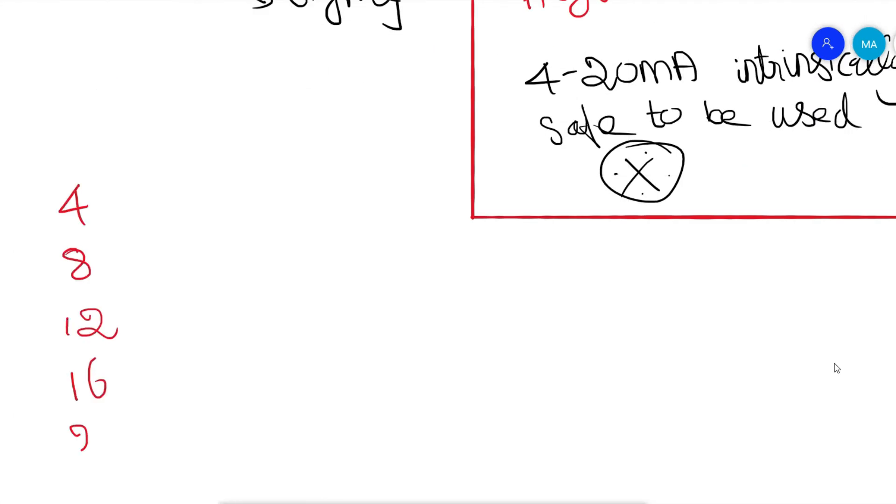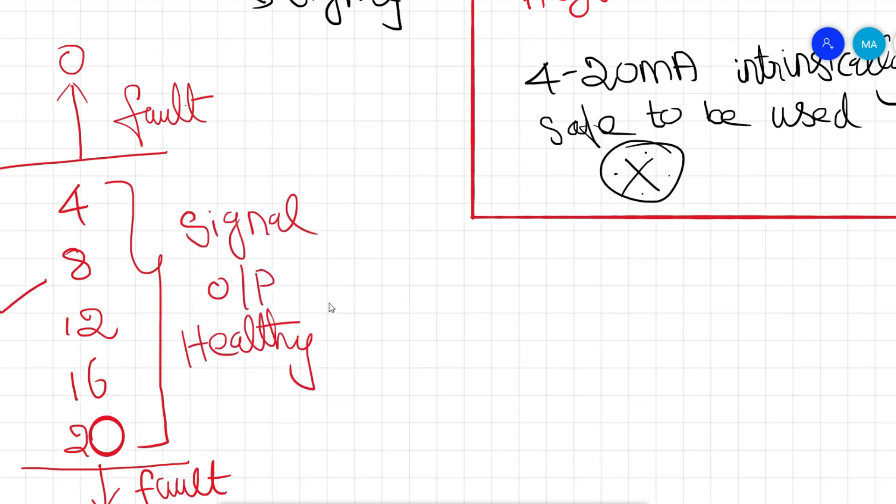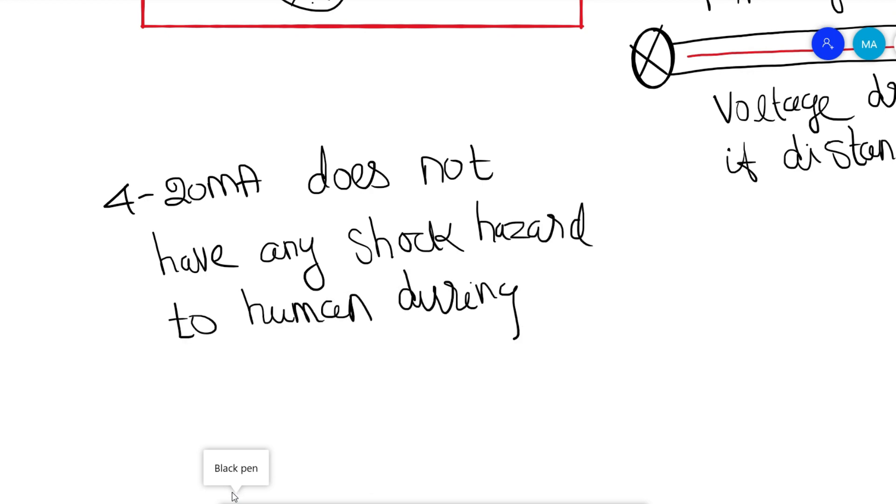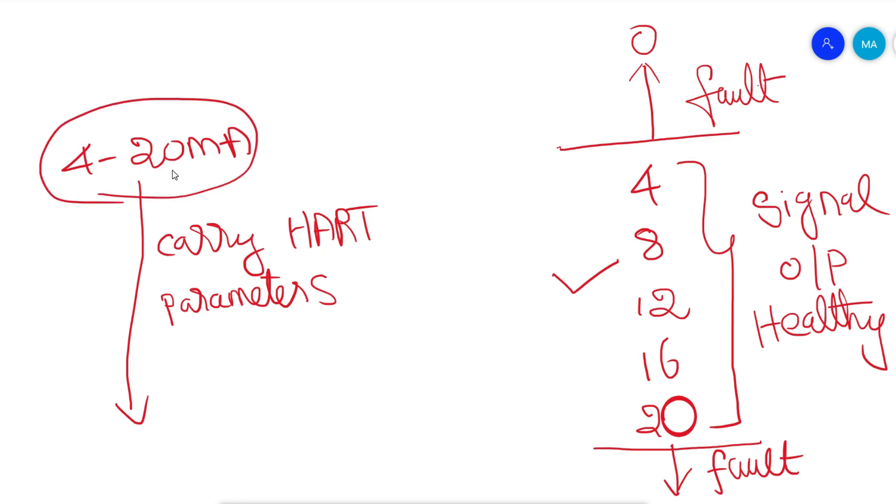Additionally, a value slightly above or below the nominal 4-20 milliamp signal can be considered as a signal or major fault. When used with a normal 24-volt DC loop power supply, no one touching the wire terminals will get shocked. The main important use of 4-20 milliamp signal is that it can carry HART digital data superimposed on its primary DC signal, carrying process and smart parameters along with this cable.